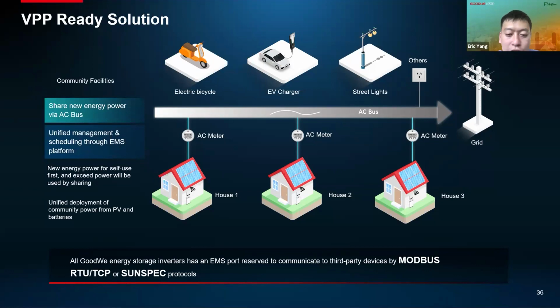Also, if the grid is not stable, we can also share the power and energy in different houses. Also, we have done some projects in the US market, like a community of maybe more than 40 or 50 houses. Each house has installed a GoodWe hybrid inverter system. And as we have introduced, all these GoodWe hybrid inverters follow the standard Modbus RTU, Modbus TCP, and SunSpec protocols. That means the EMS device can very easily communicate with the inverter to make it charge or discharge. Also, it can control the PV production.